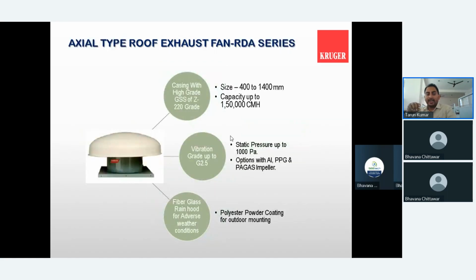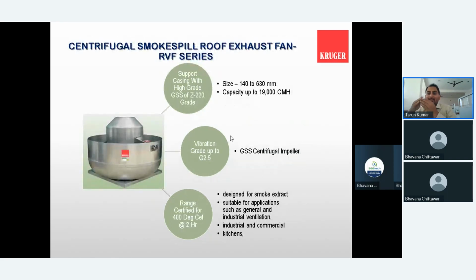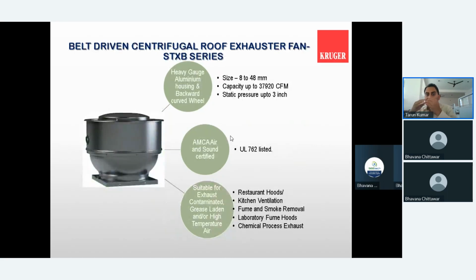Here you can see the axial fan, which can cater 1,50,000 cmh. In factory ventilation the static pressure is very low, so we can proceed with the axial kind of setup for the roof extractor fan. Whereas when the static pressure increases, for smoke spill application, we have the centrifugal smoke spill roof extractor fan, as well as a belt driven arrangement for the roof exhaust.